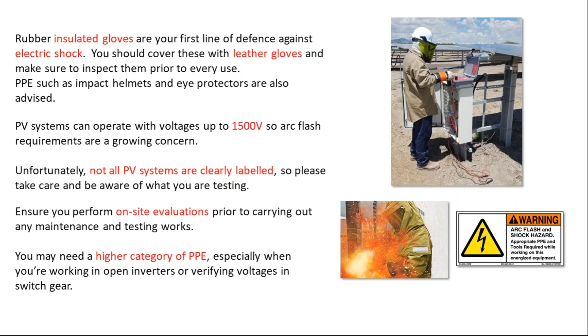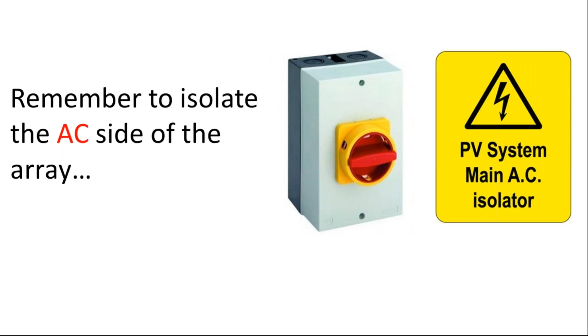And remember to isolate the AC side of the array, as we are testing at the DC side. We are testing the solar panel, we are testing the strings, so we always have to isolate the AC side of the array, and then we start the testing.